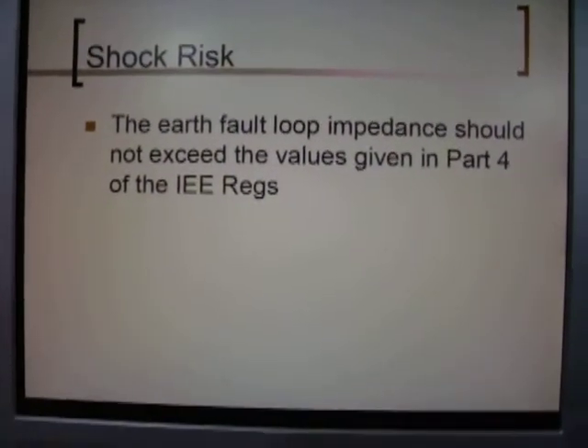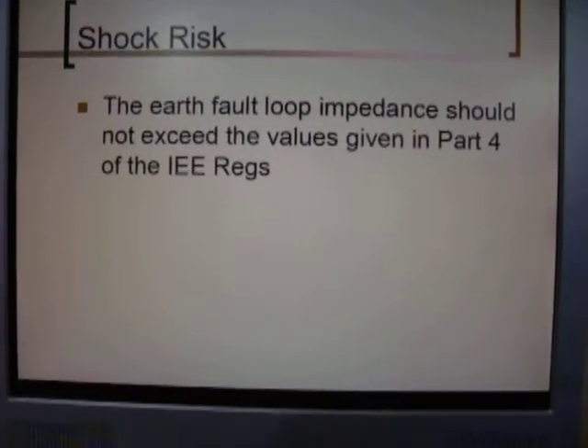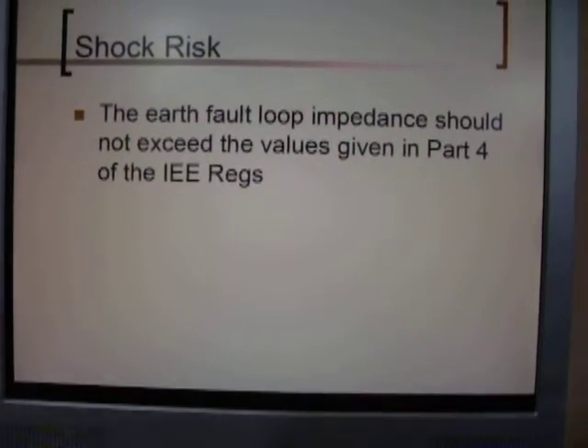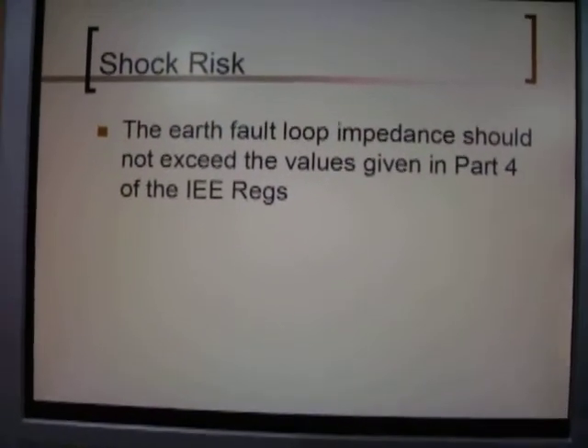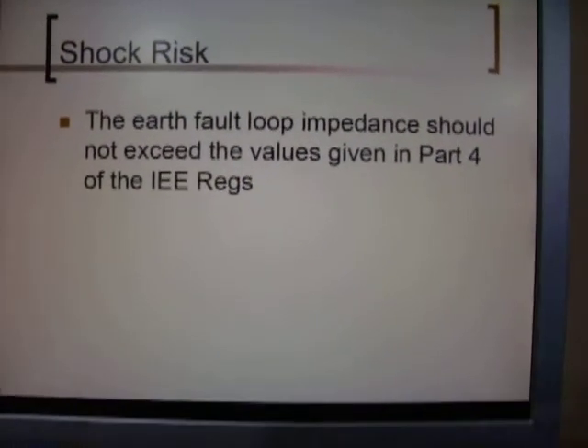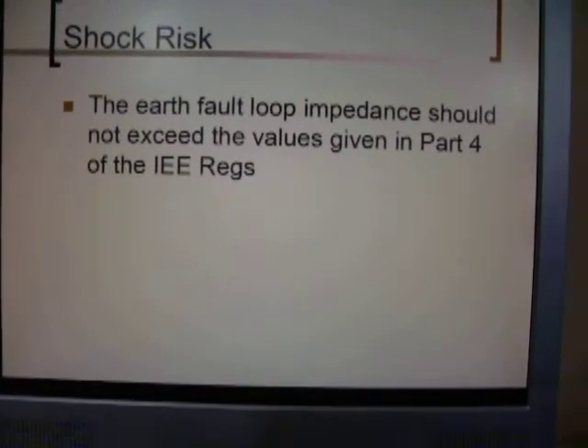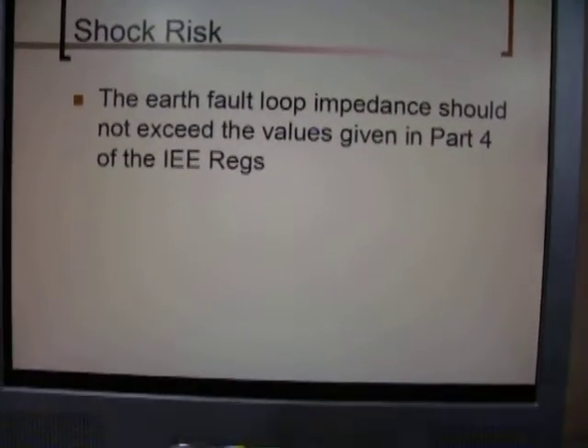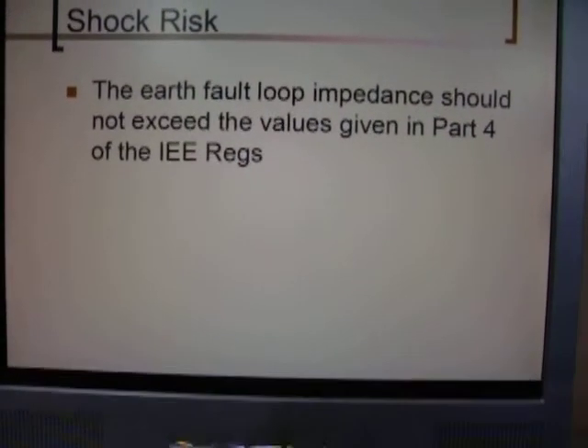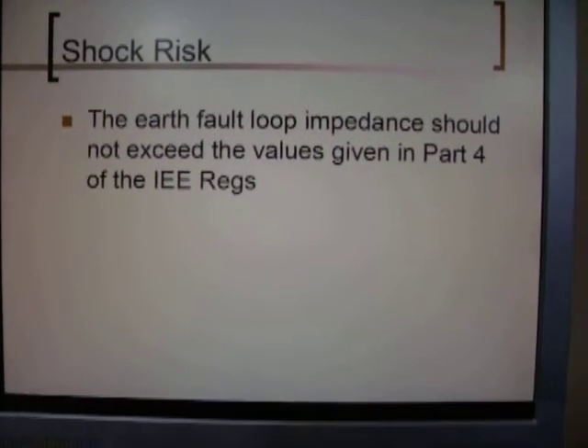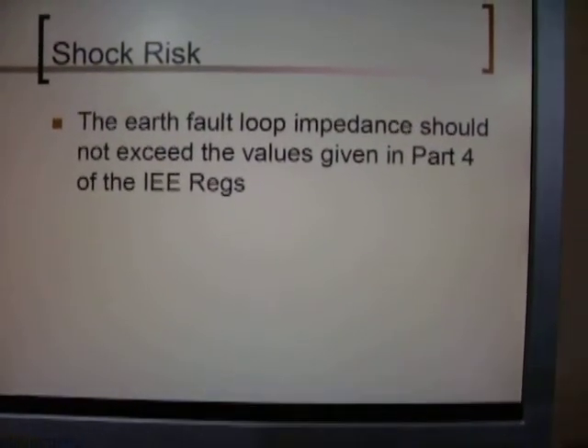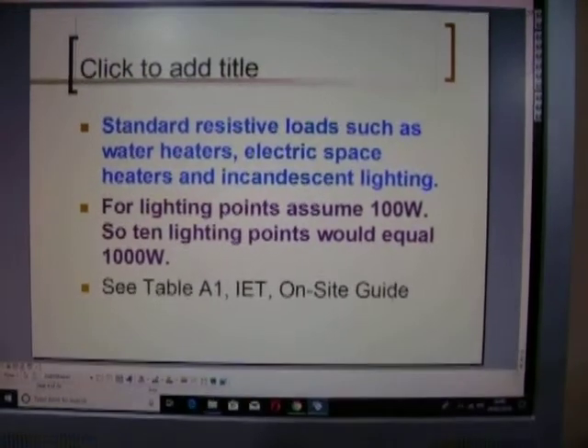Now, consider shock risk. It's telling you here the earth fault loop impedance should not exceed the values given in Part 4 of the IEE Regs. Be aware that that may have changed, even though it should still be Part 4 of the IEE Regs. Remember that our new regulations came out in 2019 from the 1st of January, so look those up and stay up-to-date.